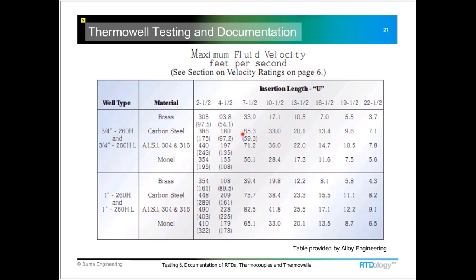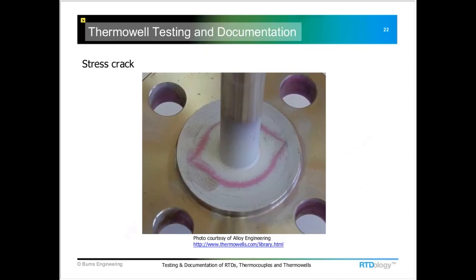the manufacturers will publish tables like this just to give you a little bit of an idea. Some manufacturers actually publish and provide the equations that are used to make these calculations, and that's pretty handy. They'll have these on their websites where you can go in and plug in all the variables and find out if the well is designed correctly for that application. If we don't do it right, we get what is shown here, a little stress crack, and this one's showing up with dye penetrant testing. That would be another test that can be done to a Thermowell, and the document that goes with that.